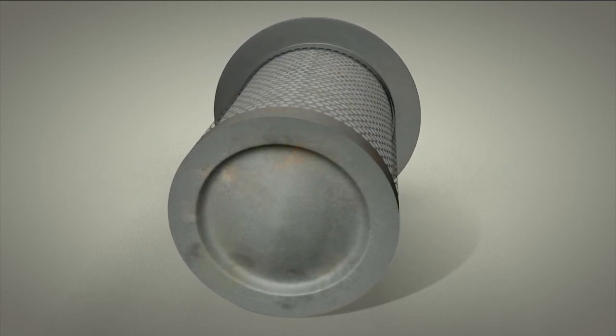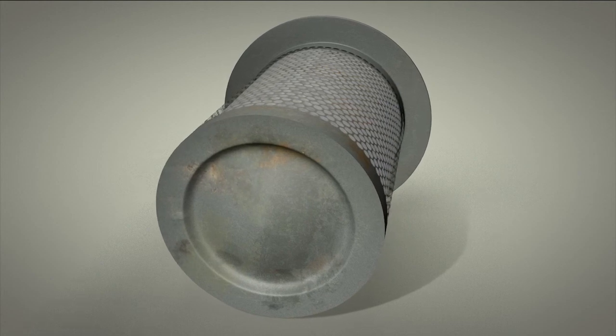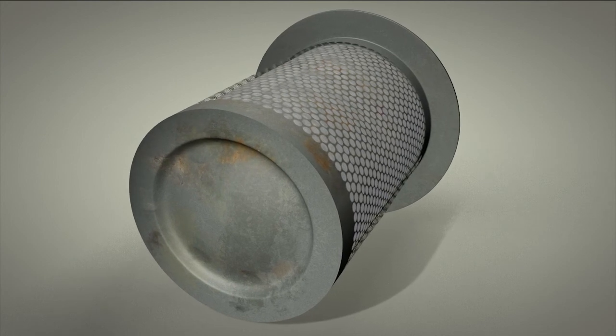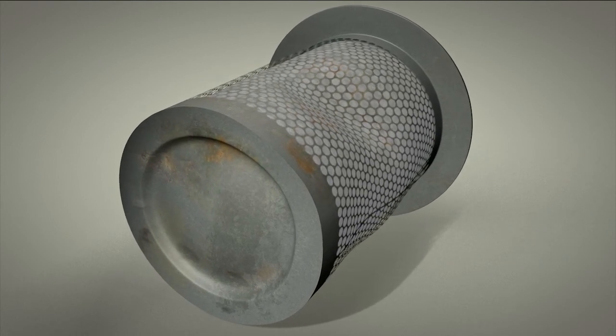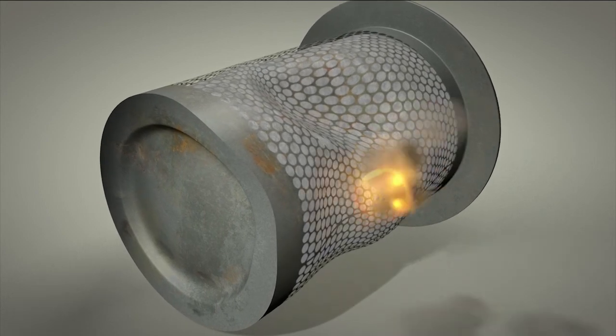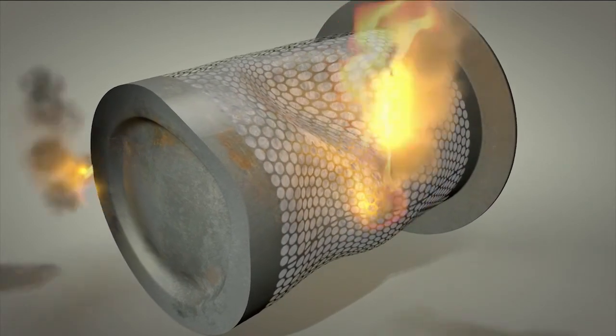Non-genuine filters may not be able to handle pressure fluctuations leading to deformation or even total failure of the air oil separator, and they are often not designed to handle the build-up of static charge which, in the worst case, can lead to a fire in the compressor.